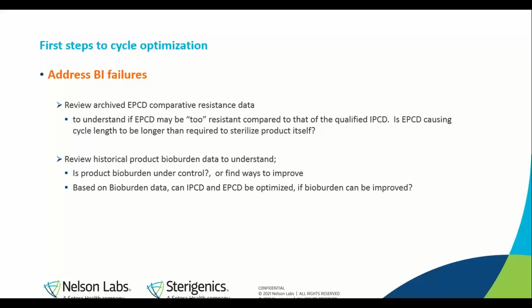So if you're having problems with BI failures, we always say look back on the historical data that you have on file for how that EPCD was generated. And recently in my conversations with some customers, I'm asking them, take a look at the historical product bioburden data. When you establish the hierarchy of resistance between the bioburden on the product and the resistance of the BI and the IPCD versus the resistance of the BI and the external PCD, that 3-layer hierarchy of resistances is important to understand which did back then with the original validation.